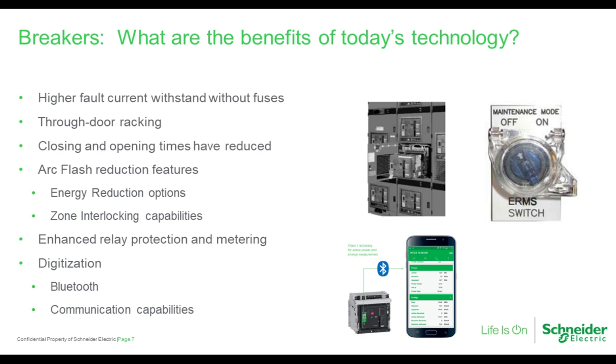Closing and opening times have been reduced. This also helps with reduction in arc flash downstream of the breaker. Arc flash reduction features, energy reduction options, the introductions of energy reduction maintenance switches so that workers can work downstream of a breaker with less potential. Zone interlocking capabilities. These also lower the risk of arc flash downstream.